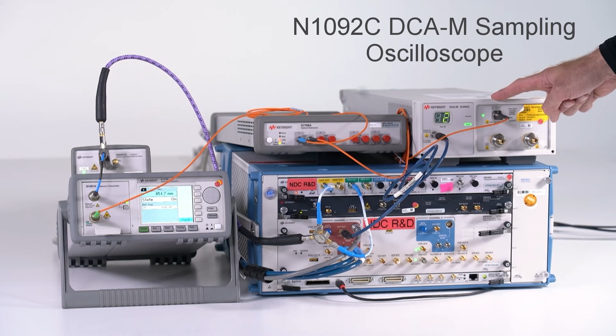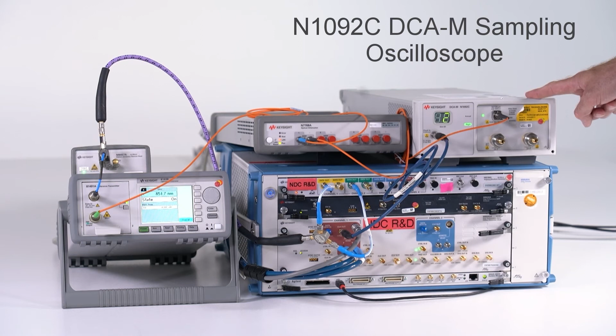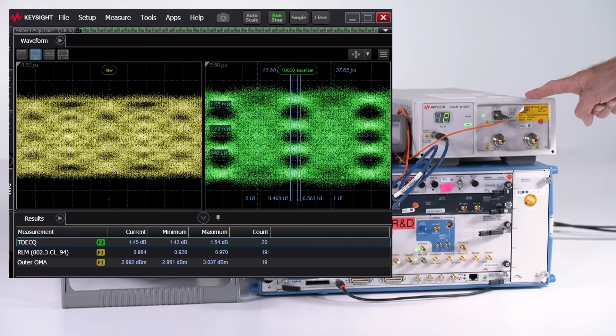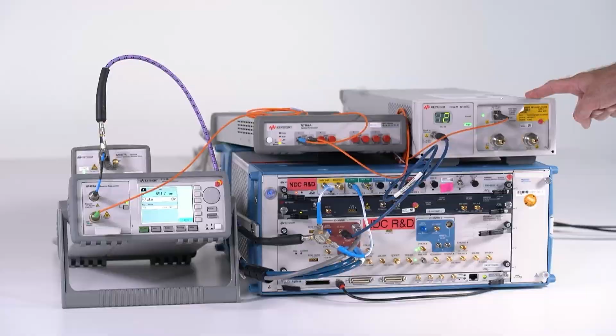The signal is then captured using an N1092C sampling oscilloscope. This model has two 50 GHz electrical ports and one optical port with up to 40 GHz 3 dB bandwidth. This scope can be configured to either emulate a reference receiver, that is with a specific receiver bandwidth and a digital equalizer, such as a TDECQ equalizer, or it can be configured to maximize signal fidelity by using the maximum bandwidth and reducing the noise. The captured signal is then analyzed in the FlexDCA software to carry out, for instance, jitter decomposition or compute metrics such as TDECQ, OMA, or extinction ratio.